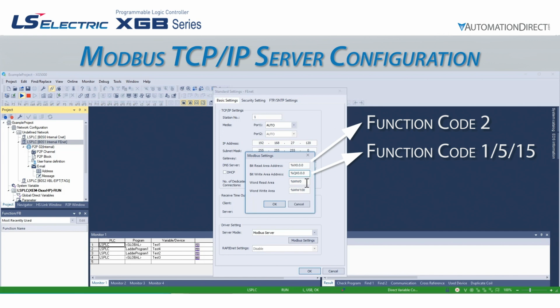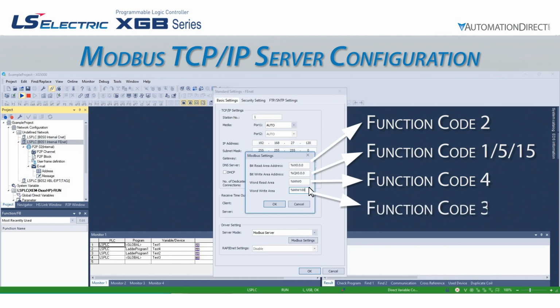The word read area will be the internal memory location starting address that will be accessible from a Modbus function code 4 read input registers. The word write area will be the internal memory location starting address that will be accessible from a Modbus function code 3 read holding registers, code 6 preset single register, and code 16 preset multiple registers.